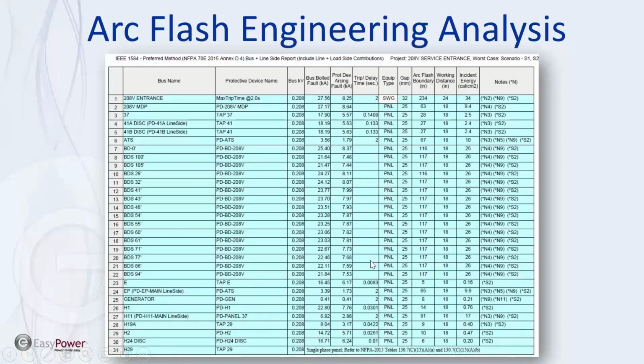All of these are 2, all the way down, 2-second clearing time. And what this means, they probably had either over-duty breakers or something where there's the default that you can use, which is a 2-second rule. And that's basically enough time for you to get away and run away from the flash in 2 seconds. If you went with what would be reasonably staying energized for 5 seconds or 8 seconds, then it would be such an unreasonably high number that it would not make any sense. So we use 2 seconds as a rule and the default in the software, which is based on IEEE 1584 standards.